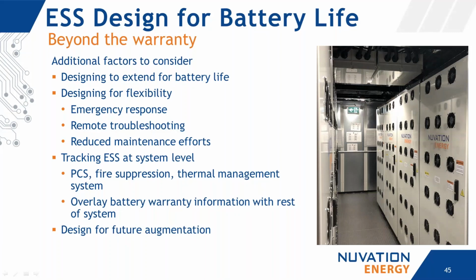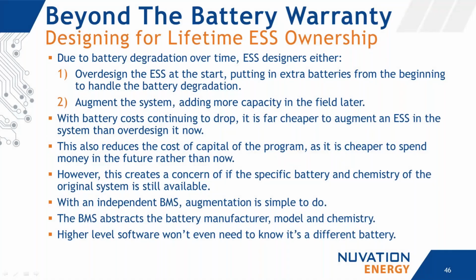Another thing we should touch on is the design for future augmentation. Due to battery degradation over time, energy storage system designers need to either over-design the system at the start, putting in extra batteries from the beginning to handle that degradation, or later augment the system, adding more capacity in the field.